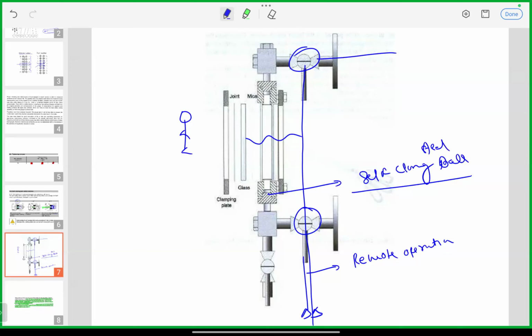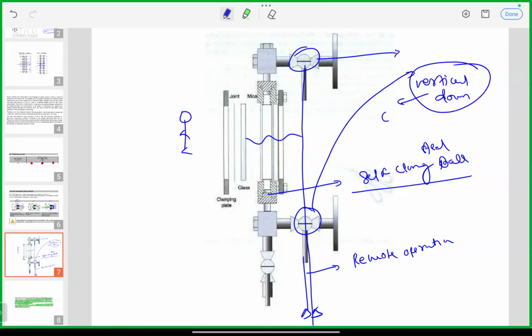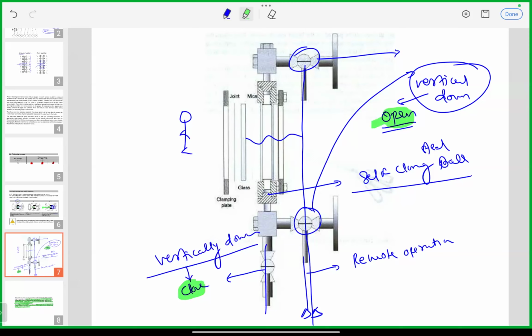Another safety is that if you look into the water side and steam side handles, they are always facing vertically downwards, and drain too, right sir? And they will be in open position. So vertically downward means open position. Drain is also facing vertically downward, but at that time it will be in closed position. So that is also a safety part, because due to vibration your valve would otherwise close. If you give the handles in horizontal position, due to vibration they are going to close.